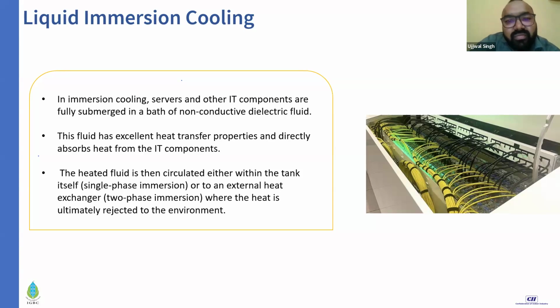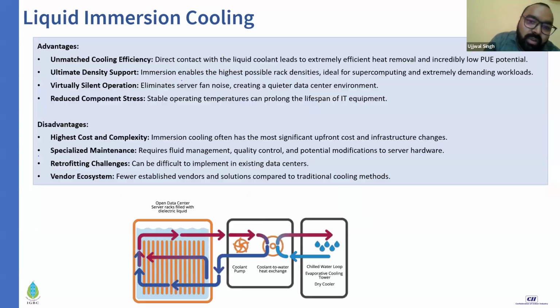So in that scenario, with liquid cooling technology, even with 35 degrees Celsius supply water temperature, you will be able to operate your data centers. Typically, there's no requirement of a chiller, just some dry coolers, or in some scenarios cooling towers. So a lot of cost is saved, there are a lot of environmental benefits, and from the PUE point of view, you can achieve a PUE of 1.03, which is the least I've seen in the world. Physically, I've seen 1.05 myself in one of the data centers in India.